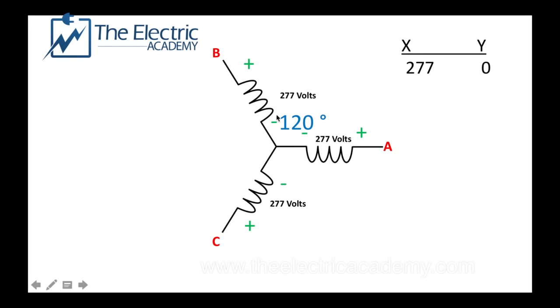Now I'm going to add in this guy here. I don't add 277 - I have to convert this to an X and a Y. The way I do that is I take the cosine of 120, multiply it by negative 277, right, because we're starting here, that's my reference. That gives me my X. Then I take the sine of 120 and times it by negative 277 to get my Y coordinate. Again, this isn't a trig lesson, so you just have to take my word for it or go watch that video on trig.